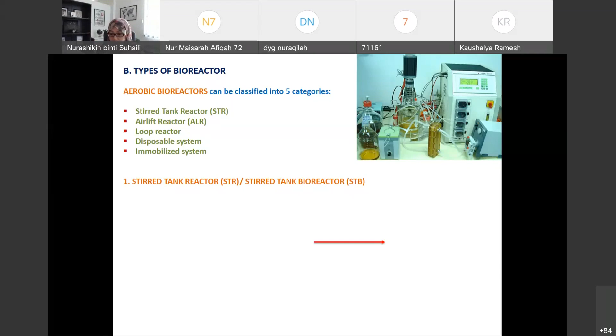The reason why it is called stirred is because it has this agitator or impeller. This agitator or impeller provides the mixing. It will agitate the contents, and it is connected to the motor. When we connect this motor to the electricity, it will turn on and mix the contents inside. So the whole system is actually not shaking. It's just static. It's just this part that is moving, and that's how the culture inside is mixed. That's why it is called stirred tank. The mechanism is by stirring.